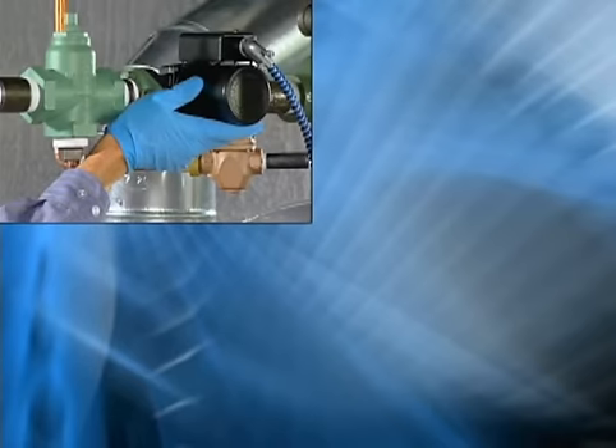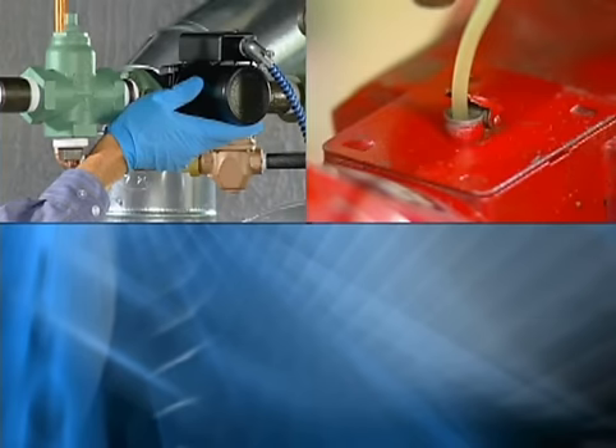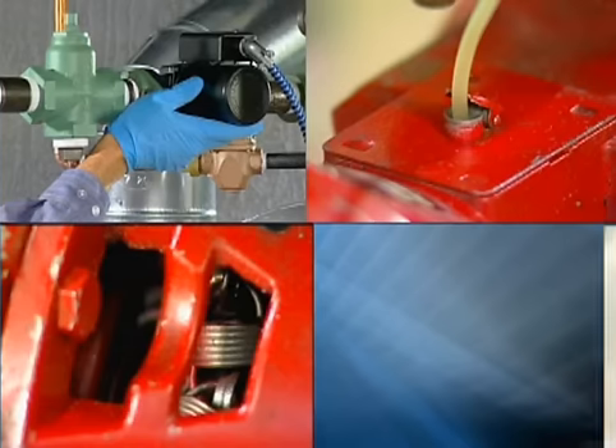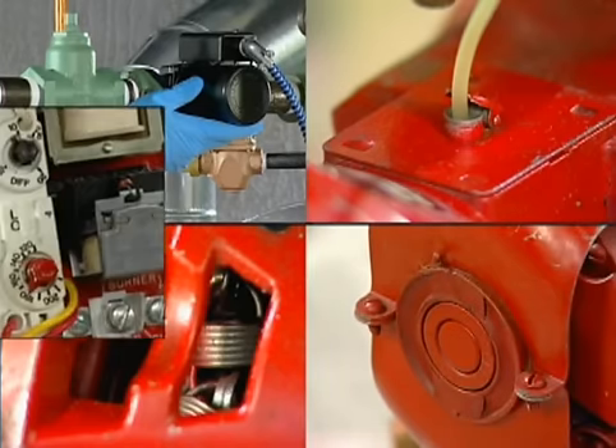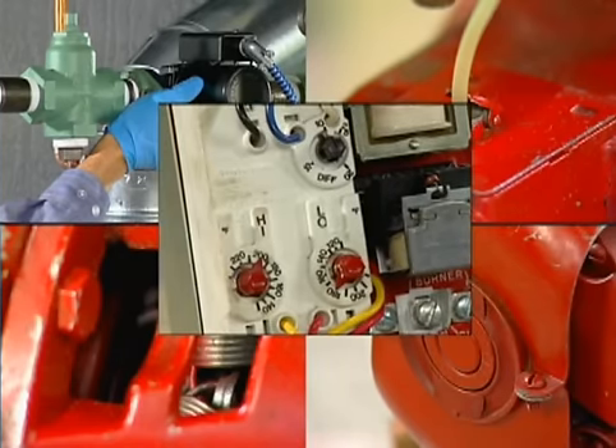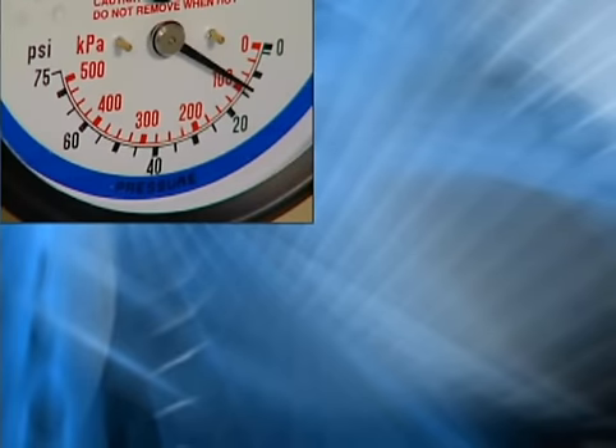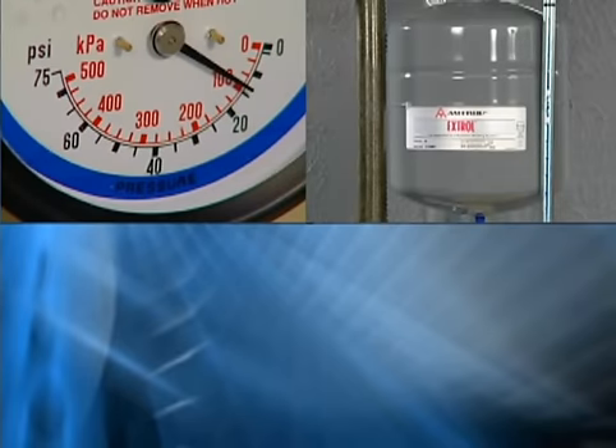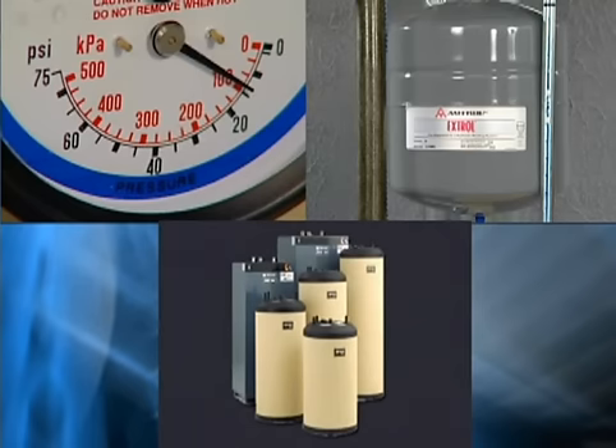Check the circulators and/or zone valves to be sure each operates properly. If applicable, lubricate the circulator motor and bearing assembly. Check the circulator couplings and motor mounts. Check the control settings to be sure they'll provide for proper heating, hot water, and circulator operation. Check the system pressure and the expansion tank. If there's an indirect water heater, check the circulator and control.